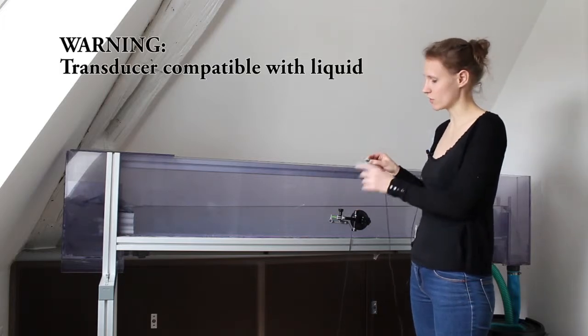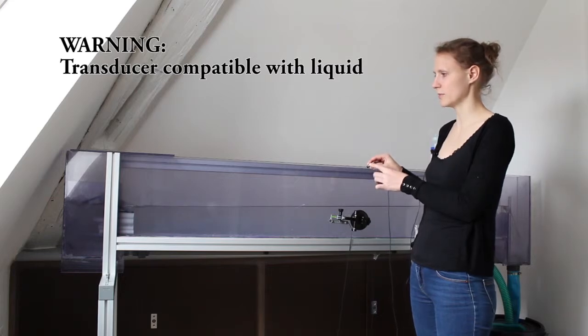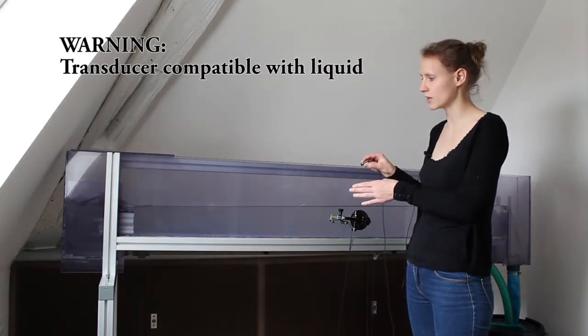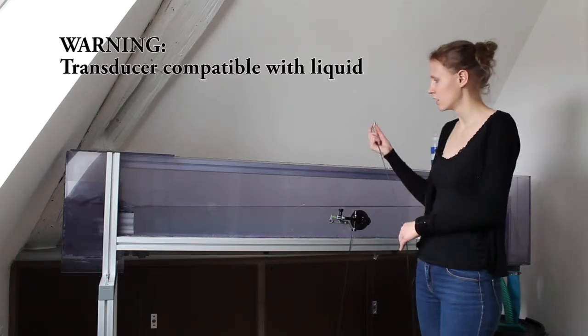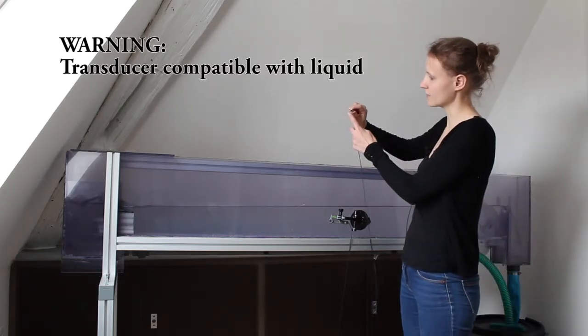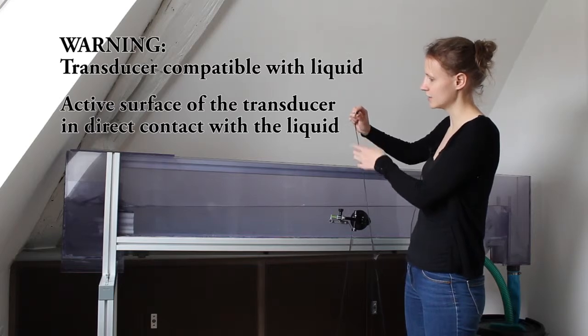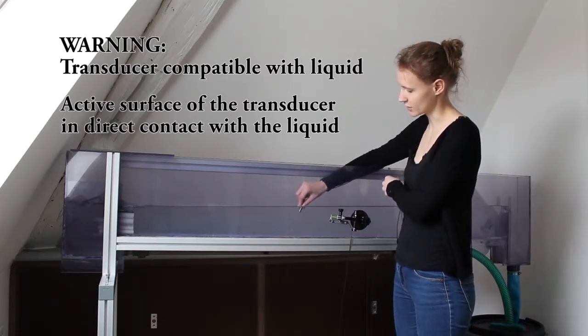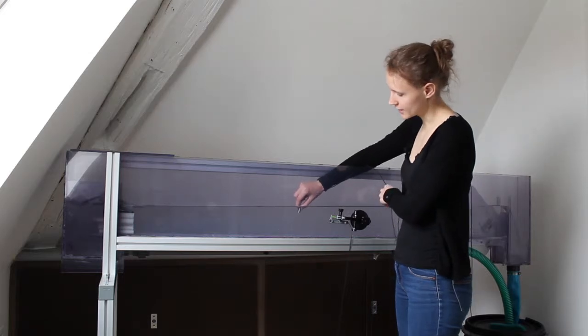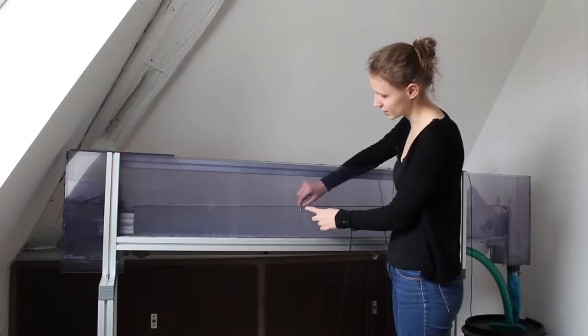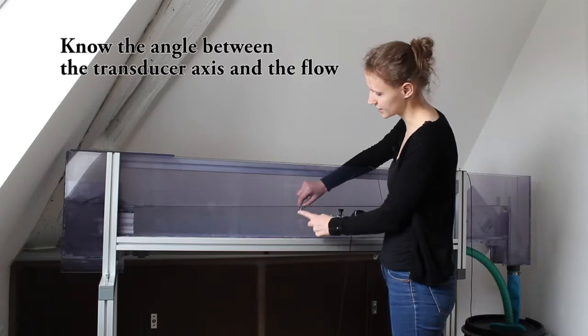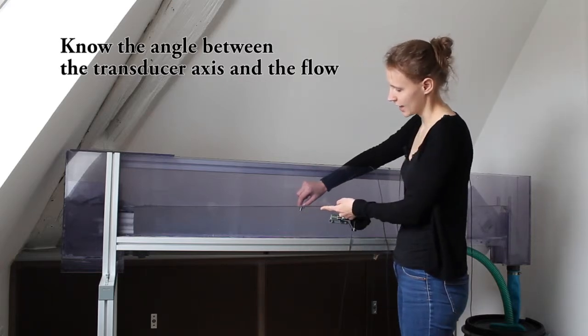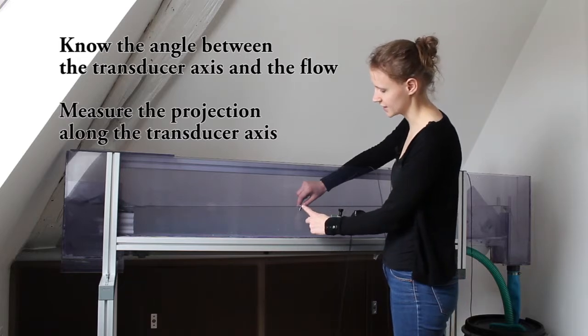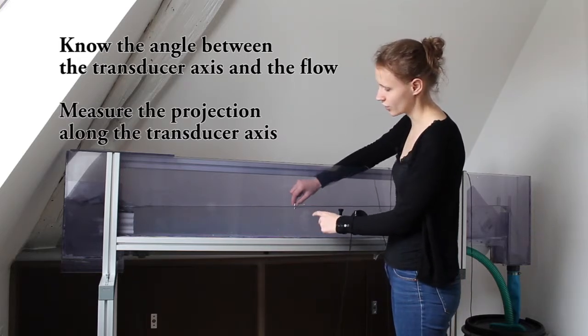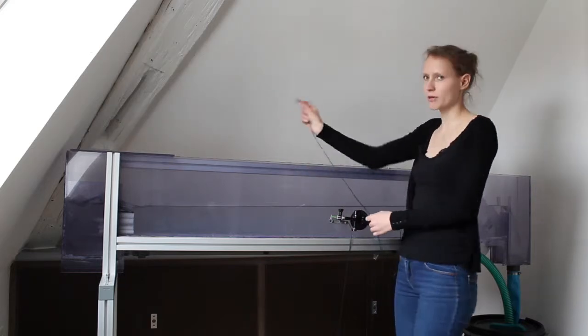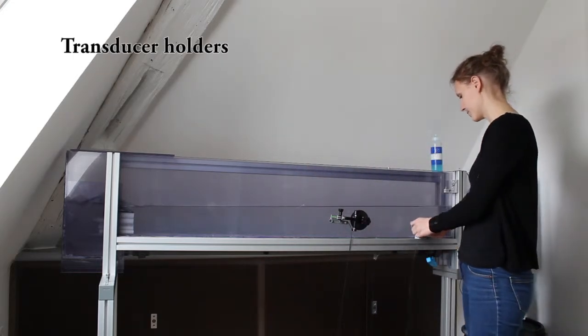Here it's water, so there is no problem with those transducers, but you may be working with corrosive liquids or in harsh environments. So you can put the active surface of the transducer, in black here, directly in contact with the water. When holding it manually, you will not know the exact angle between the transducer axis and the flume. And as we measure the projection of the velocity along the transducer axis, you want to know the angle. So we recommend to use holders.